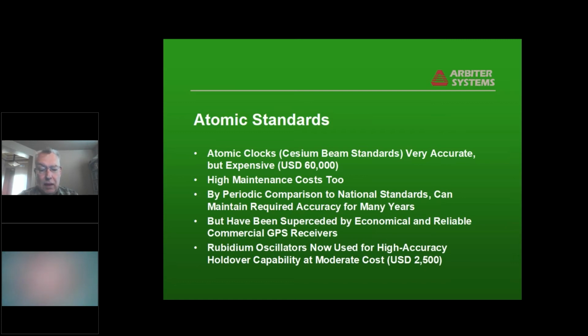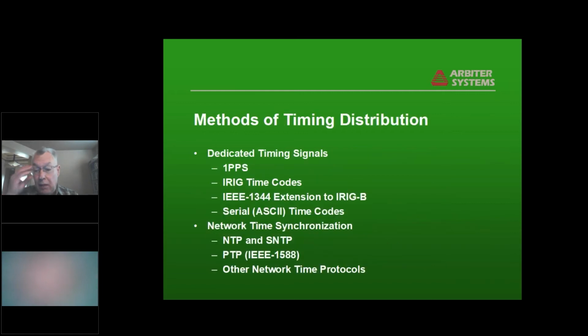Rubidium oscillators are being used now for high accuracy holdover capability in substations, capable of maintaining timing of roughly a microsecond a day in the event of a fault to the GPS system or an antenna or something else going bad that causes loss of the GNSS time. That adds only about $2,500 to the price of a clock. So if you have a critical substation where you want to make sure that even if you lose GNSS time, you have an accurate backup, that's a viable possibility. Those aren't a fundamental standard like cesium is, but their frequency is quite accurate, and more importantly, they have very good stability.